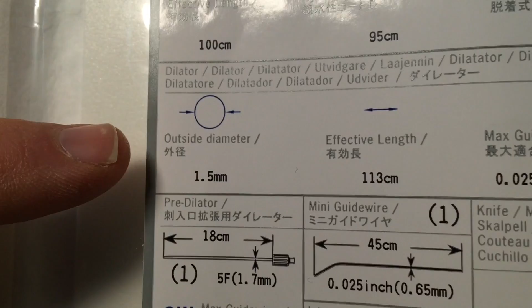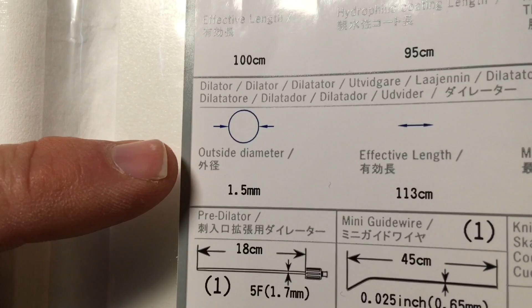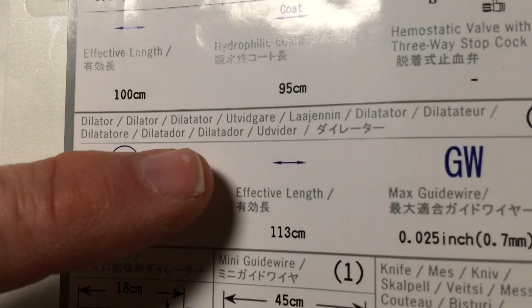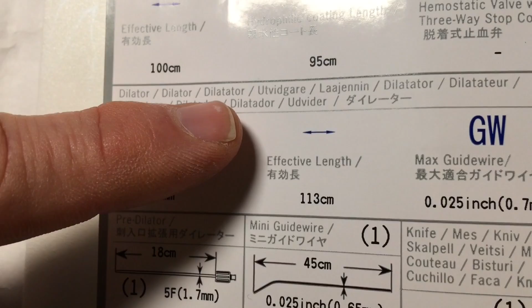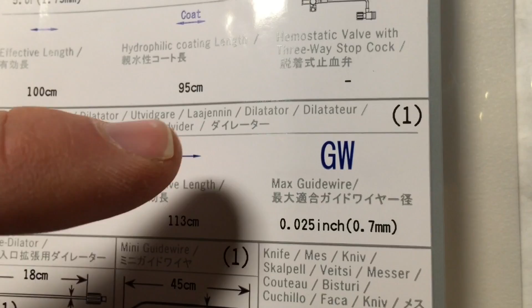The dilator instead has an external diameter of 1.5 mm, is 113 cm long, which means that it's longer than the guiding catheter, and will accept a guide wire of 0.025 inches, which is thinner than the usual guide wire.